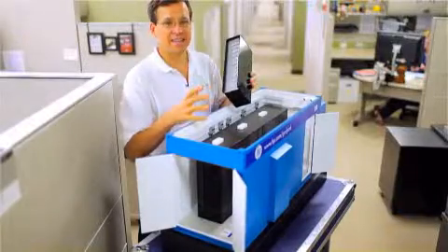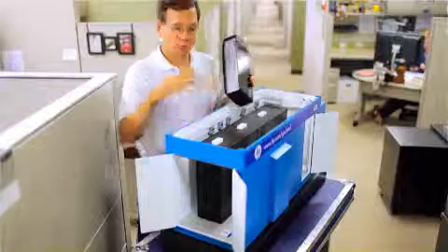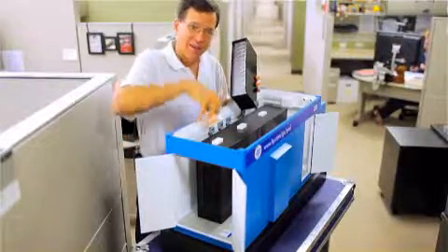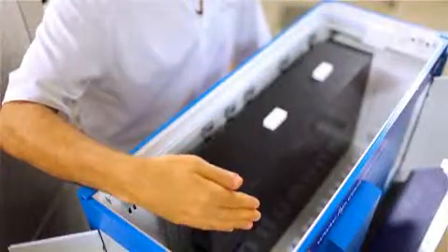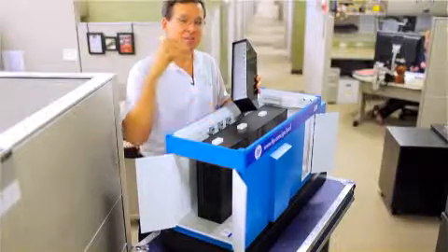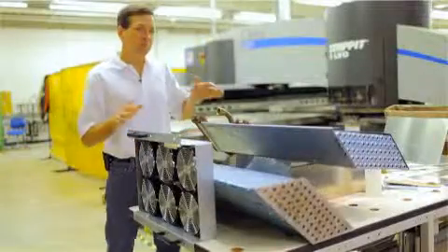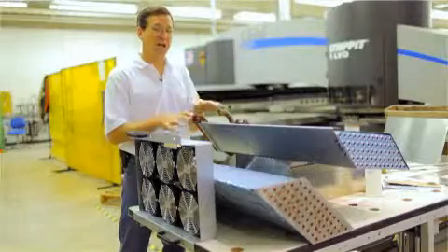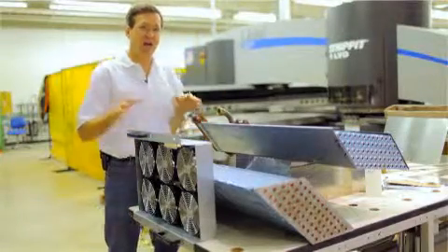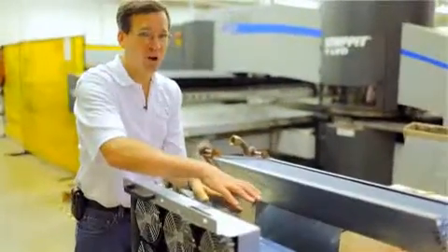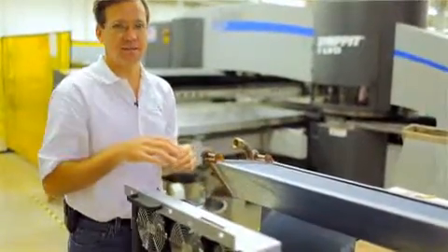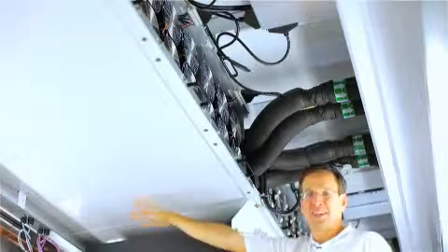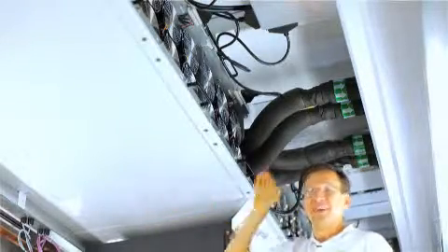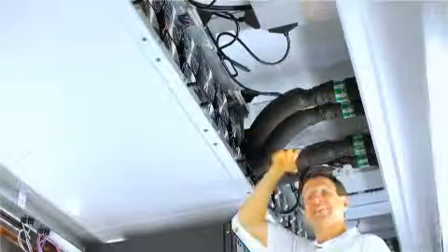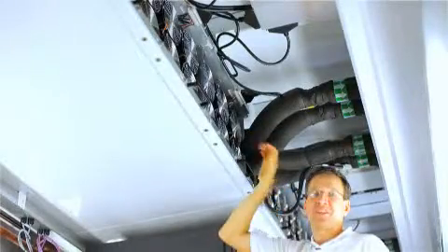All this IT now has to be cooled. We want to take the waste heat coming out of the hot aisle and cool it off using the least amount of money and using the least amount of energy. Some people think you trade efficiency for reliability, but our design allows for enterprise class fault tolerance. There are redundant fans and coils for concurrent maintainability. Cooling just like your data center, where the server waste heat is sucked through the coils and injected down as cold air as efficiently as possible.